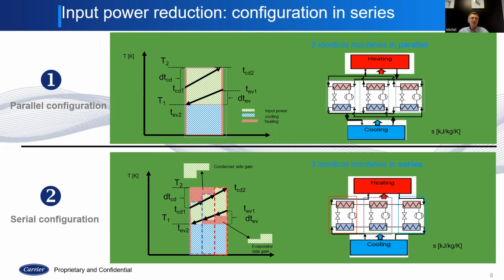Without entering too much into details, everybody knows the parallel type of configuration. The same leaving water temperature is seen by each of the units operating in the group. You can have 2, 3, 4, 5 units, and each of them sees the same entering and the same leaving temperature on both the evaporator side and the condenser side. If you try to represent what happens inside this kind of system, I'm simplifying here by using the Carnot cycle, so it's a kind of ideal cycle, which our refrigeration cycle tries to be as close to as possible. So it's not 100% representative of what we are doing in air conditioning, cooling, and all types of thermodynamic machines, but it's close enough to analyze directionally how things behave.